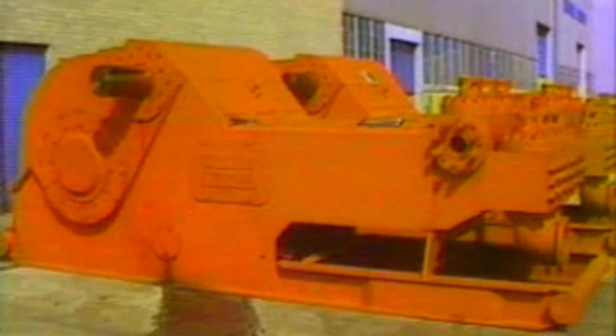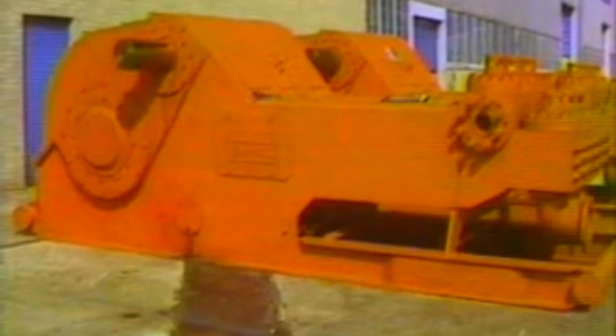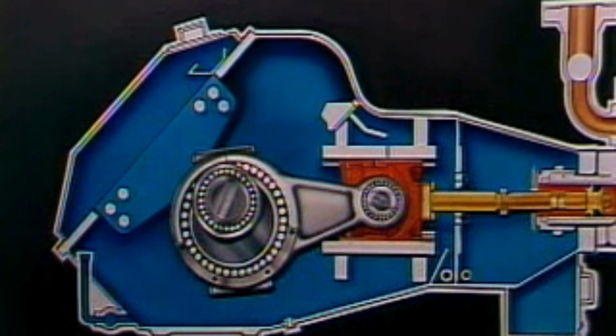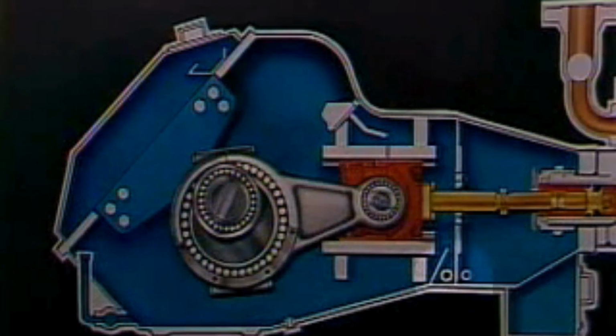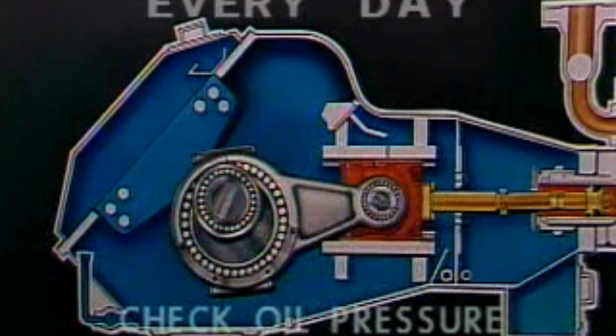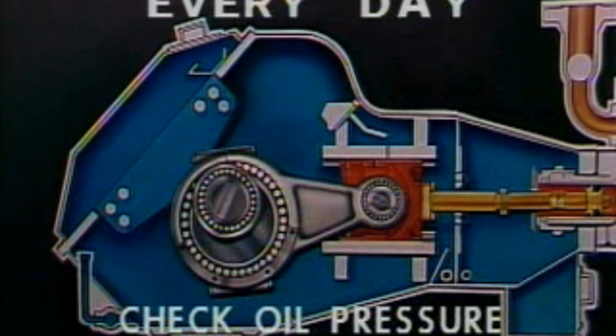Some pumps have no external oil pump or filter systems. These pumps rely on the main gear to carry lubricant up to a system of troughs which supply oil to the bearings and crossheads. There are a few procedures you should follow every day to keep your pump in good condition. Check the oil level in the crankcase. Drain the sludge from the mud trap. And check the oil pressure and temperature. These don't take long, and they're easy to do.